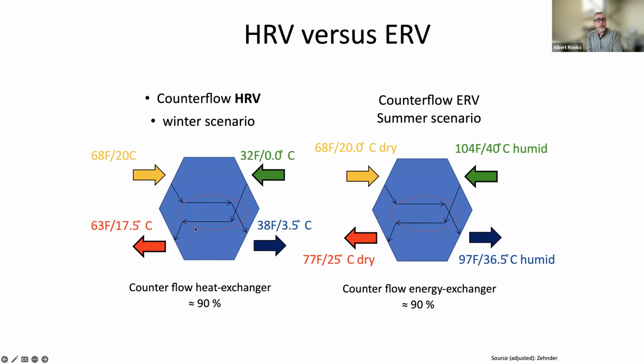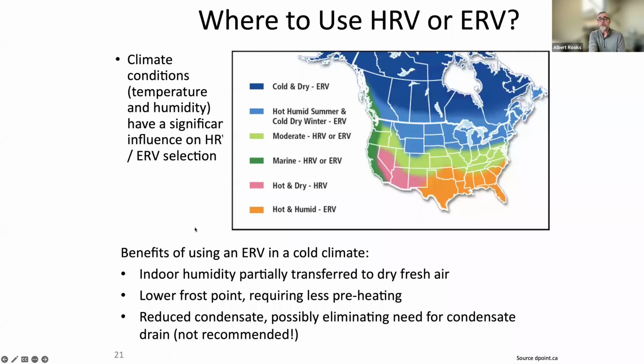And the cooler dry air is going to come in, and because the moisture is leaving on the lower right, it's not going to pick up moisture on the inside. So if we deploy an ERV in Atlanta, Georgia, we're going to essentially keep the high temperature moist air outside the building. And if we do the same thing in Tahoe, we're going to keep the cold dry air on the outside of the building, and we're going to keep moisture on the inside of the building. So that's kind of how we manage it.